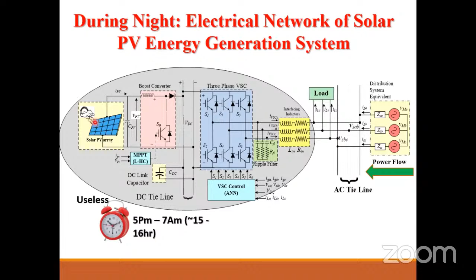Is there any way we can use this system at night? Definitely the sun will not come at night, so we cannot generate that way. But can we use it for a different purpose? The answer is yes. We can use this small section of the circuit at night as a STATCOM or DSTATCOM, depending on the conditions. This means the converter, filters, control, and capacitor can be used at night as a STATCOM to generate reactive power and support the grid, or as a DSTATCOM to generate compensating currents for nonlinear local loads and support the grid.